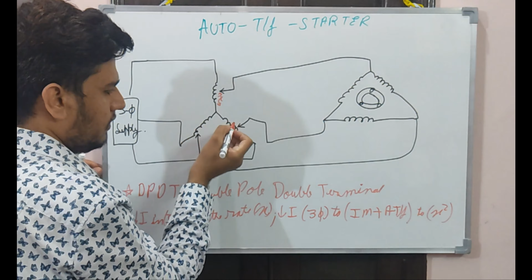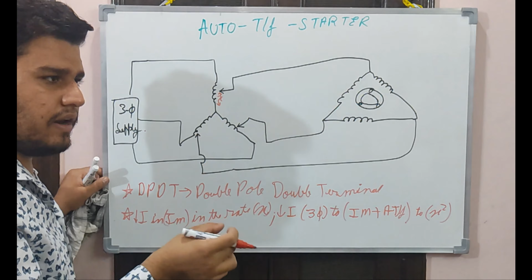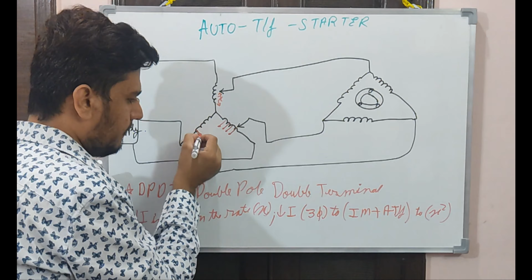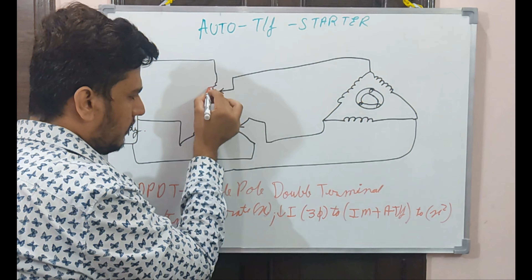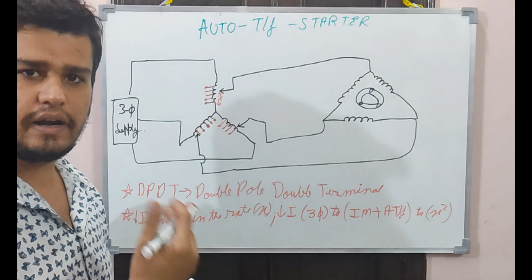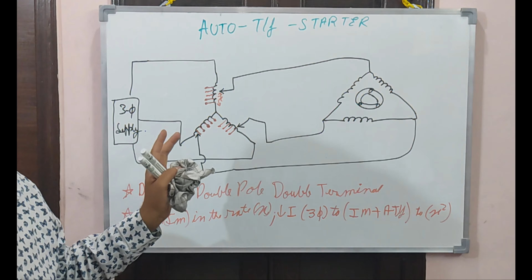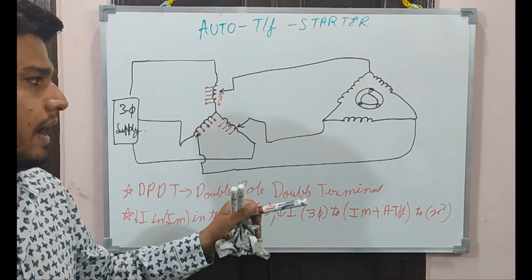This is done by different types of tapping. The regulators are not connected so that you can regulate them to any point; instead, the auto transformer is pre-designed with different types of tapping, and points are connected as per the rating you want to control your current to. After the induction motor reaches nearly 80% of its rated speed, the transformer is disconnected and the motor starts running at its rated speed.